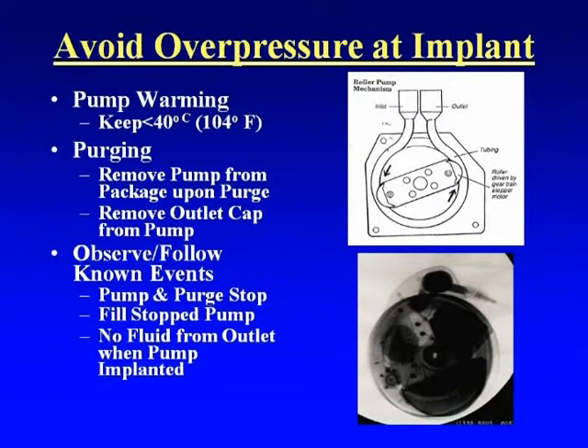Overpressure can also occur from heating. Remember, the bellows is surrounded by a halogenated gas that puts pressure on the bellows, pushing it closed to push the drug to the rotor, so the drug gets delivered to the rotor tubing and the rotor can push it out. So if patients go into a hot bath, the pressure in the system can increase, and you can get increased pressure going to the tubing to the rotor.